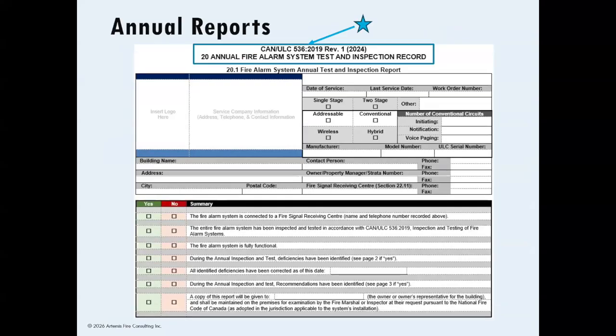A complete test record for a fire alarm system and all devices should be a minimum of 16 to 17 pages, with 19 total sections numbered from 20.1 through to 23.3. Section 23.2, the individual device record, will potentially have dozens of pages recording the testing required on every device attached to the fire alarm system.